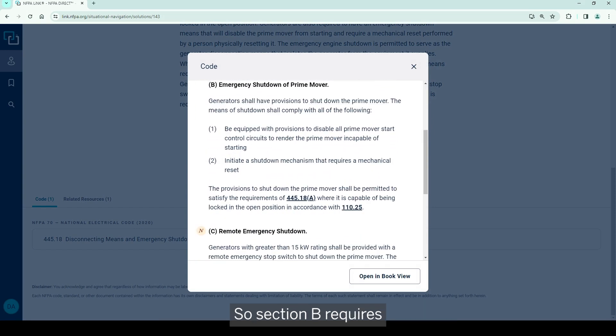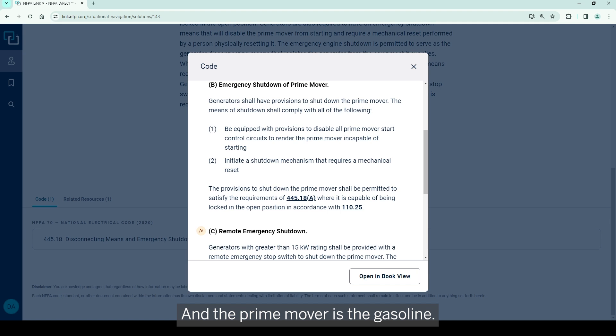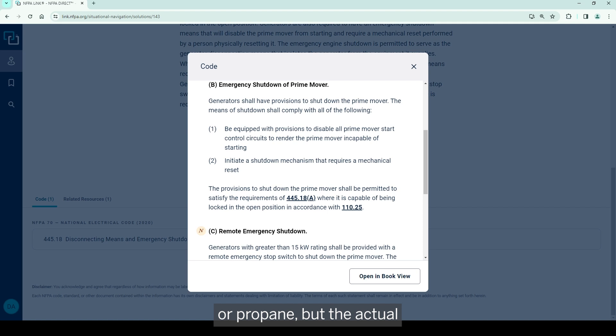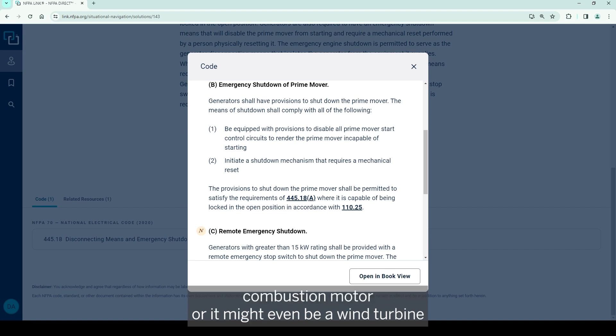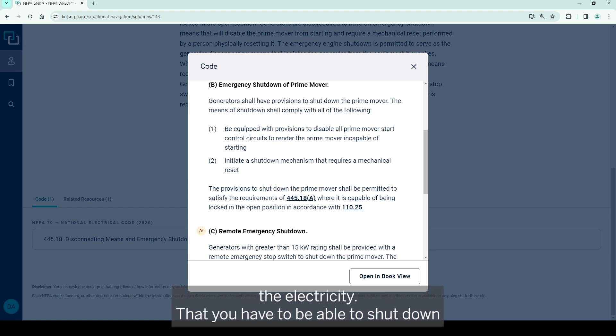So section B requires an emergency shutdown for the prime mover. And the prime mover is the gasoline engine - typically gasoline, might be natural gas or propane, but the actual combustion motor. It might even be a wind turbine that is actually spinning the electrical motor that produces the electricity. That you have to be able to shut down.